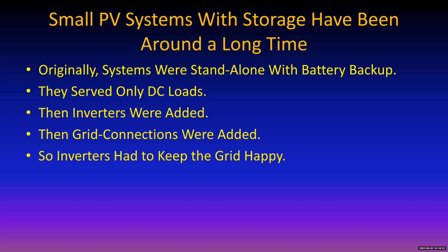Synchronizing the output of an inverter takes roughly 3 or 4 milliseconds, so it really doesn't take very long to connect an inverter into the grid. The only thing is, the inverter will not start feeding the grid for 5 minutes, because it's going to monitor the grid and make sure the grid is stable before it starts feeding electricity. But then it turns on and keeps the grid happy.